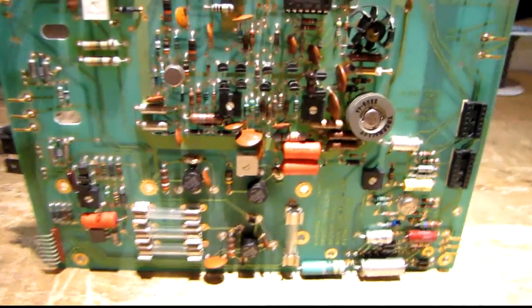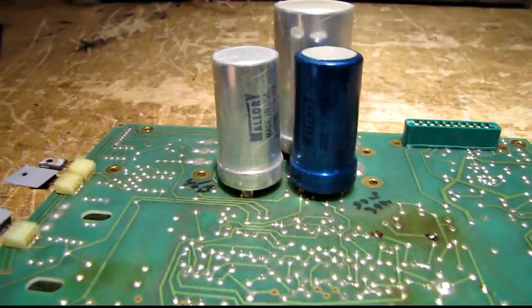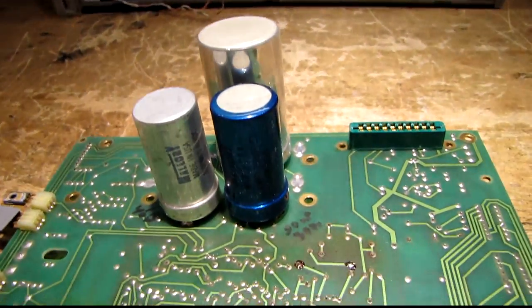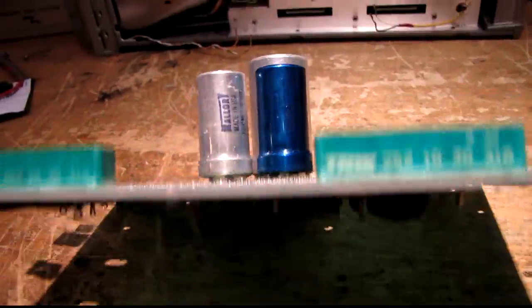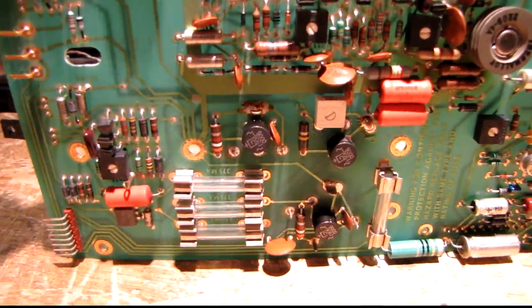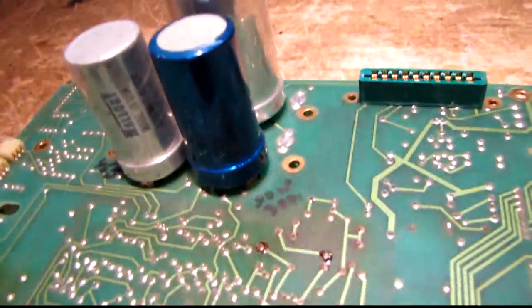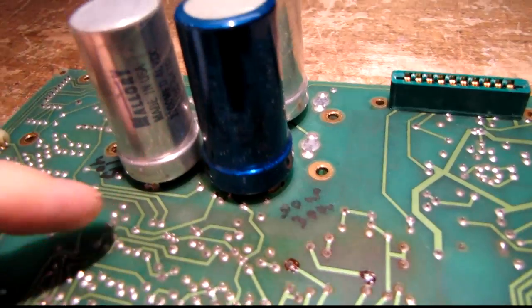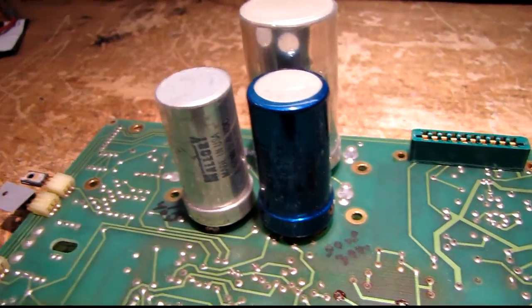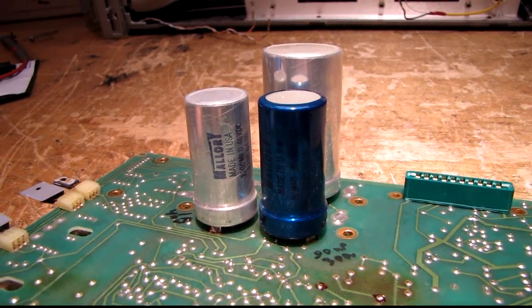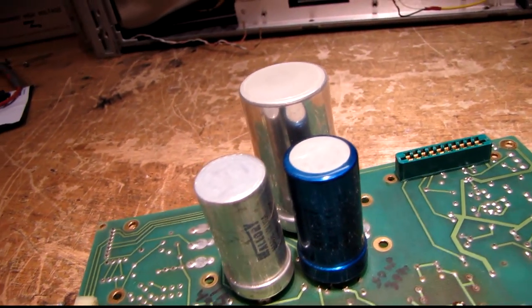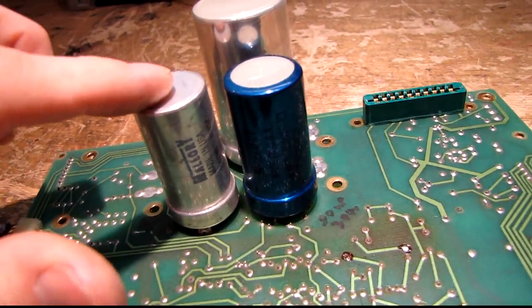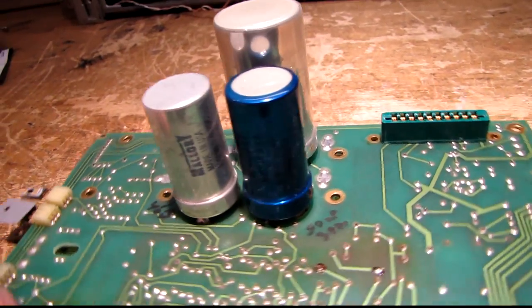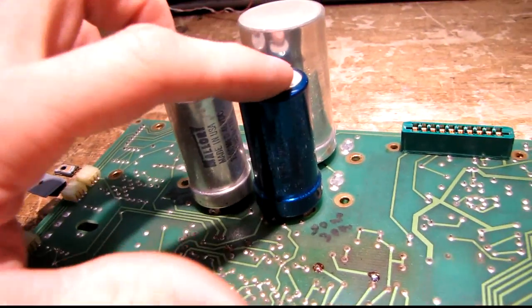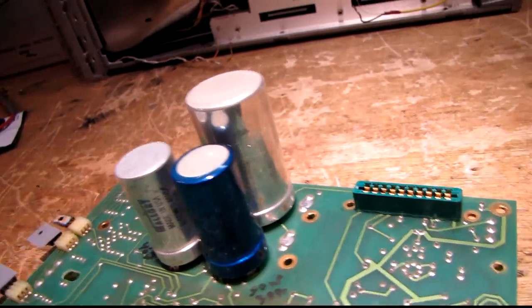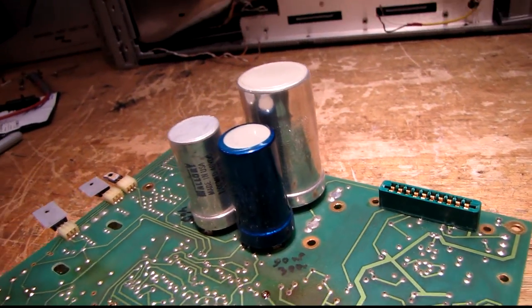Now I do have the schematic, but it's a little old and hard to read, so I'm going to take note of where each of these wires are going so I can disconnect them and pull this board out. Well, I've got the board removed now, and it looks like I'm going to have to take these filter caps off to replace the bridges because they're directly underneath them. So I wrote a note on the board here which cap goes in which spot for these two smaller ones because they're completely different ratings. And I don't want to get them backwards because one of them's a high voltage cap and one's a low voltage cap. This one's 40 volts, this one's 300 volts. Definitely don't want to get those reversed.